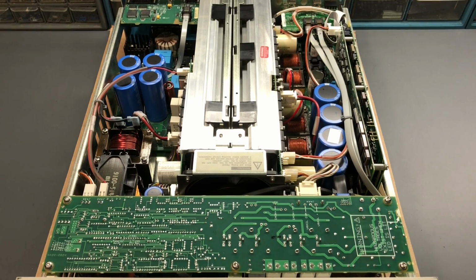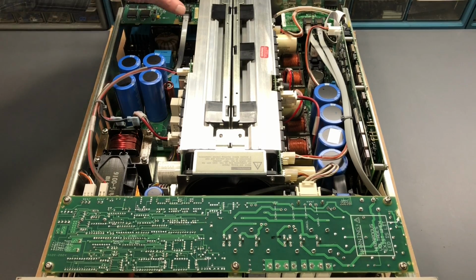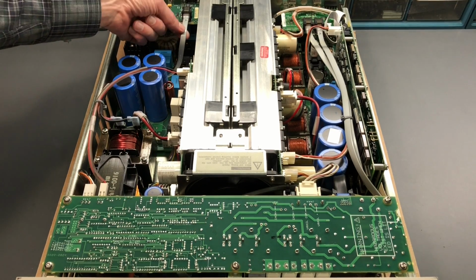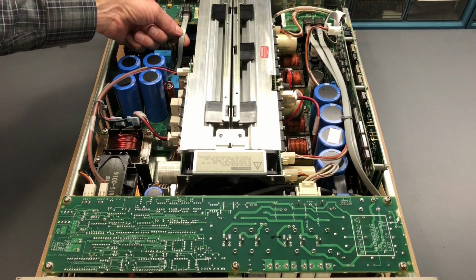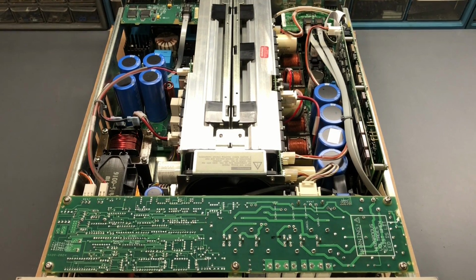So for the sake of completeness, let's take a quick look at the main component locations within the AC power source. I'll also get the block diagram of the instrument. We'll go over that real quick just to make sure we understand how the instrument actually functions internally. And then I'll get the top cover in place and we'll try and power it up for the first time. So in this back corner right here is the GPIB and RS-232 interface board. The only connection to that board internally is this cable right here on this RJ45 connector.